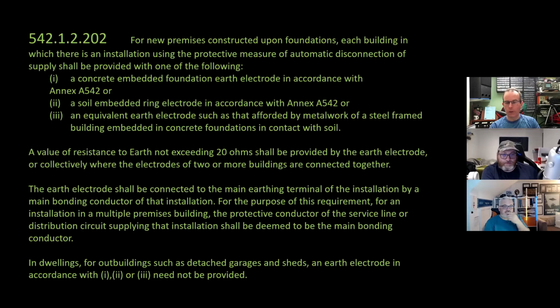And also, one interesting thing, the value of resistance to earth not exceeding 20 ohms. I have a letter, and you can Google it, from Ofgem to the Wiring Regulations Committee from about 12 years ago, that says to them that they should not be recommending 20 ohms as a value, that they should actually be working at the rising voltage under fault, which never made it into the wiring regs, and that came from Ofgem. So I don't know why they didn't do that, but we'll cover that in DNO webinar part 2. We'll have that on the screen.